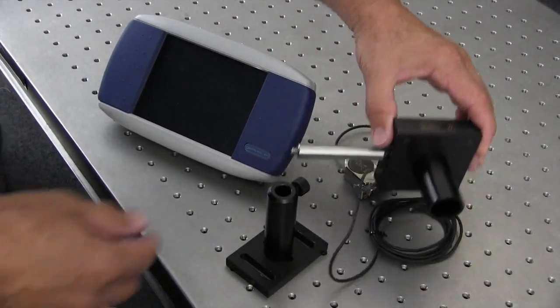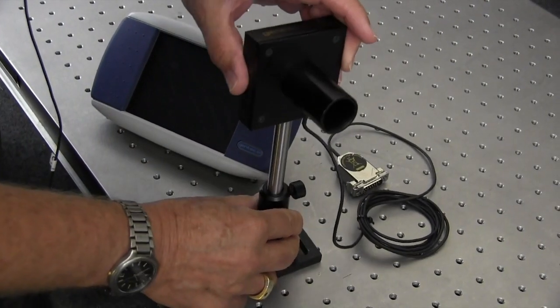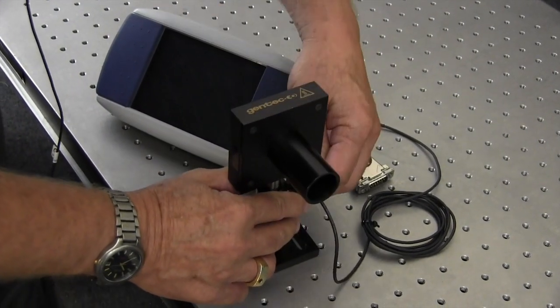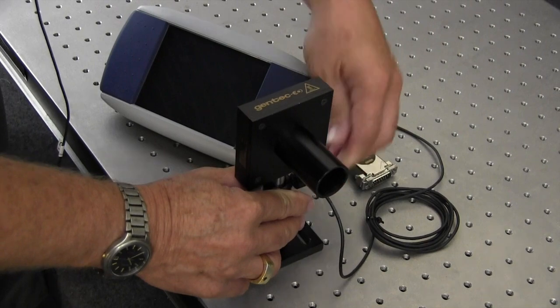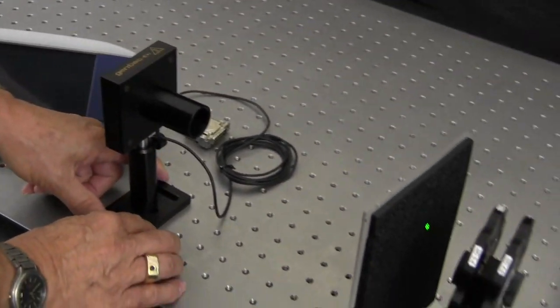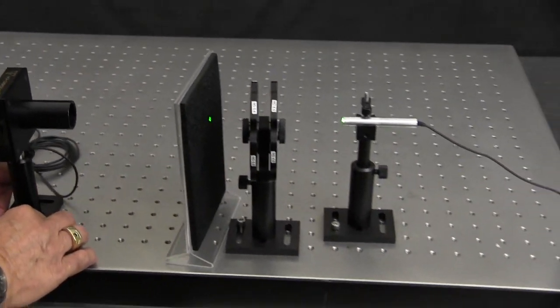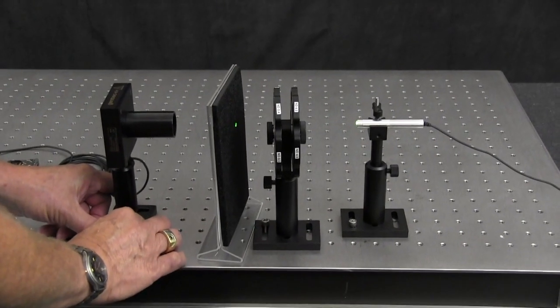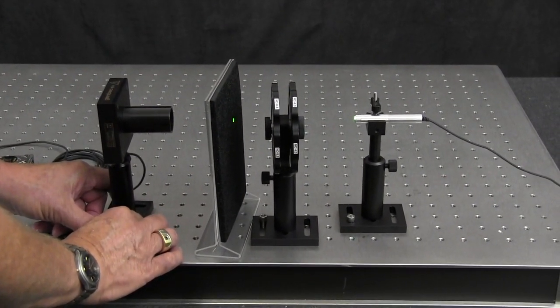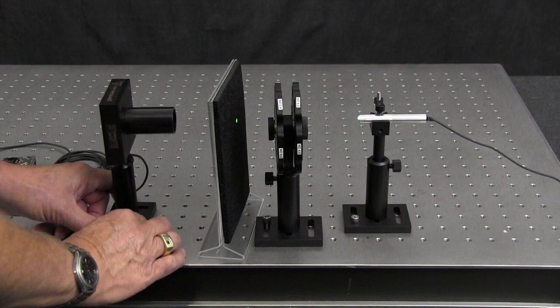Mount the XLP12 to your optical table, making sure to use one of our metal posts as it is part of the heatsink for the thermal probe. Then we need to move the probe close to the source you're going to measure. This effectively cuts down the field of view to minimize background radiation.